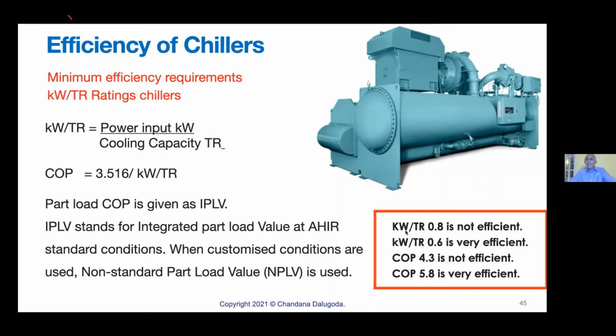Now, if it is in kilowatt per ton, 1 kilowatt per ton is baseline, but it is not efficient at all. 0.8 is not efficient. 0.6 kilowatt per ton is taken as efficient equipment. On the contrary, in COP, on the other side, COP 4.3 is not efficient. COP 5.8 is taken as efficient.